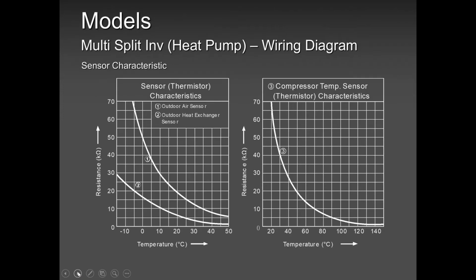Then in our service manual or on our app, you have this chart. If you think the sensor is a problem, always refer to this chart. All our sensors, guys, are rated in kilo ohms. The moment you get an open ohm reading, you have a problem. The moment you get a fluctuating up and down reading on a sensor, you have a problem.